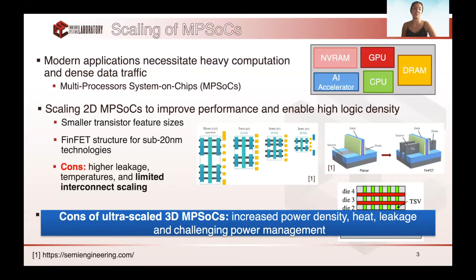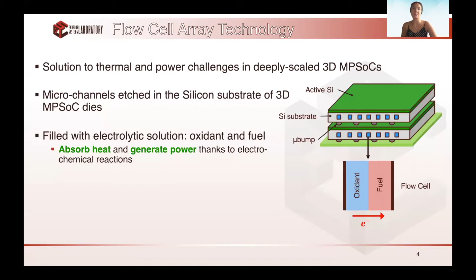In this context, the flow cell array technology, or FCAs, was developed as a solution to the thermal and power challenges of 3D MPSoCs. The FCAs are microchannels that are etched in the silicon substrate of the stacked die. These channels are filled with an electrolytic liquid that serves two main functions. First, it absorbs the heat and serves therefore as on-chip liquid cooling. And second, the electrolytes chemically react as the temperature increases, and they generate an additional power that can be used in the 3D MPSoCs. The FCAs have been prototyped, and an electrothermal model has been developed to enable simulating their performance in different 3D MPSoC architectures.